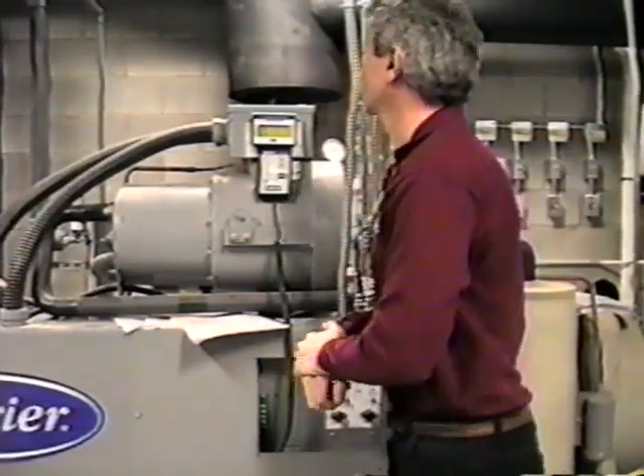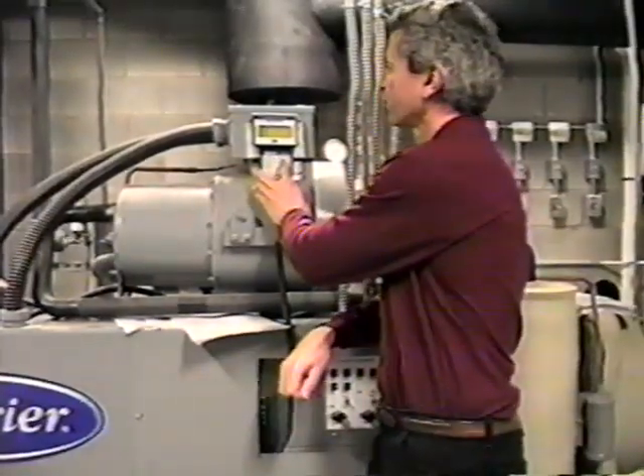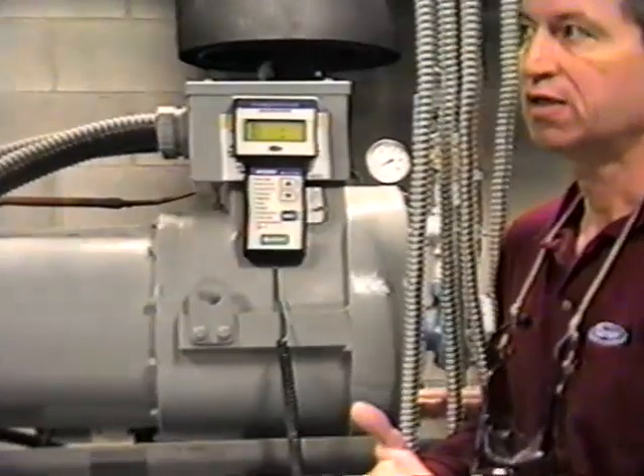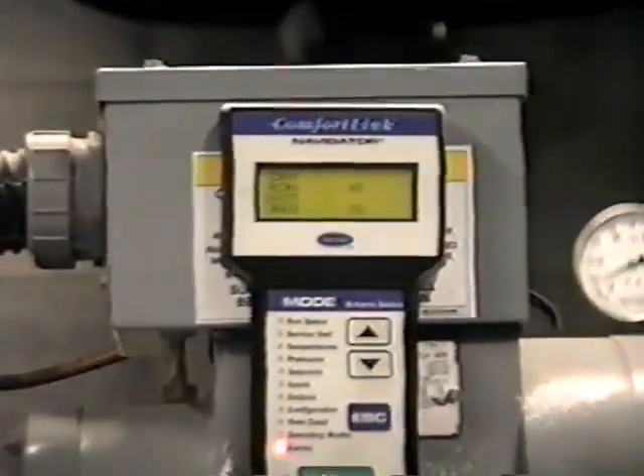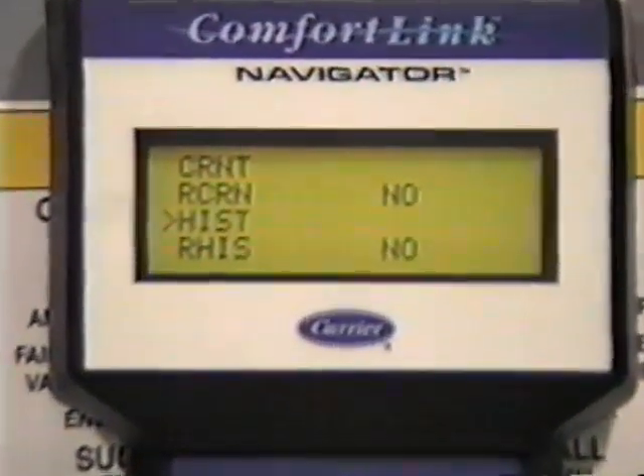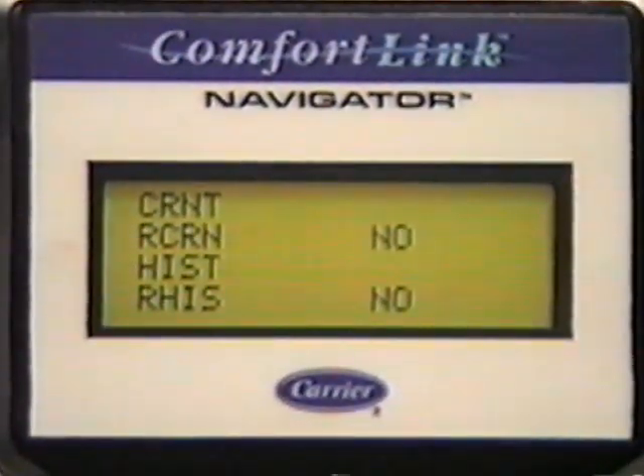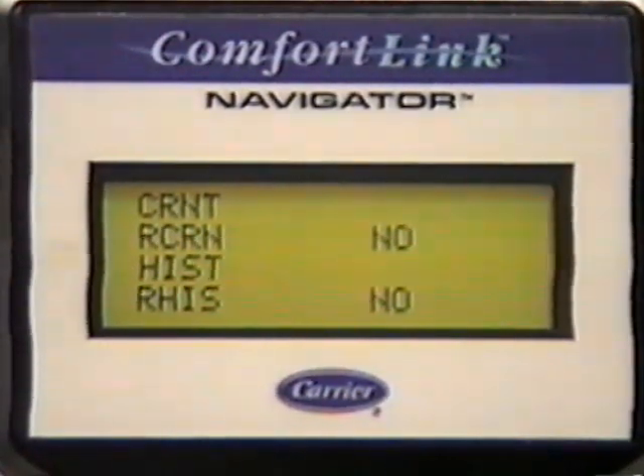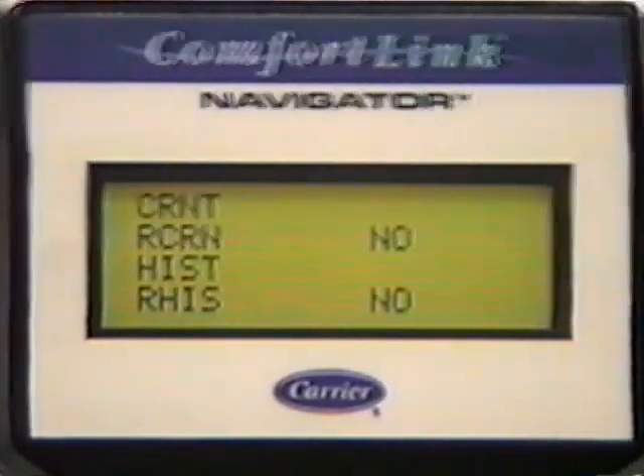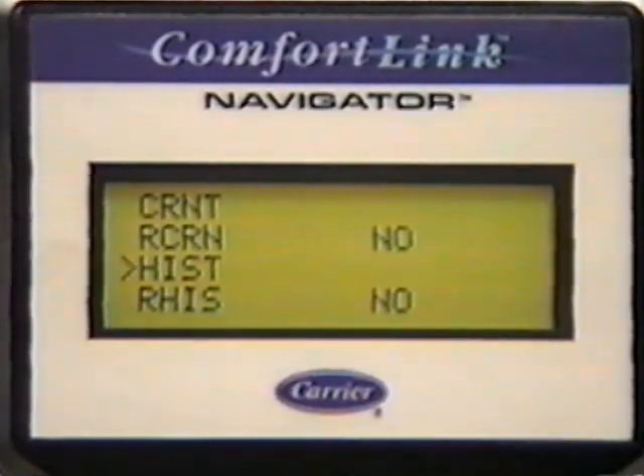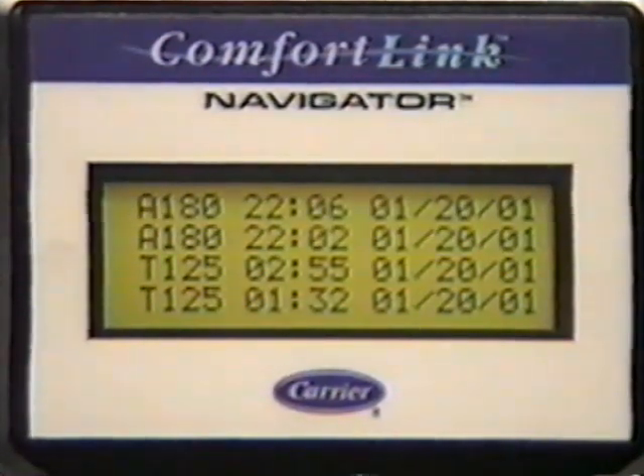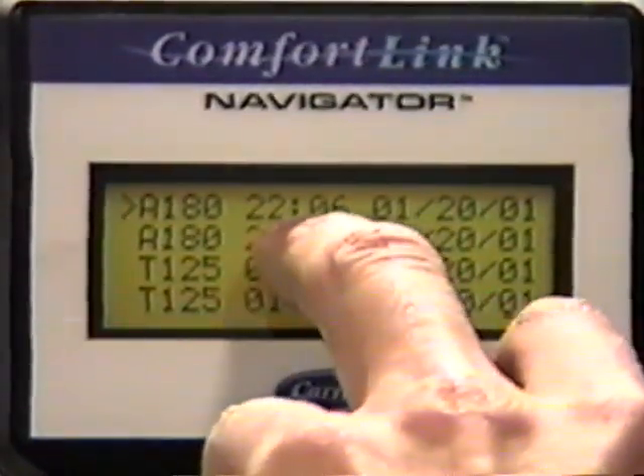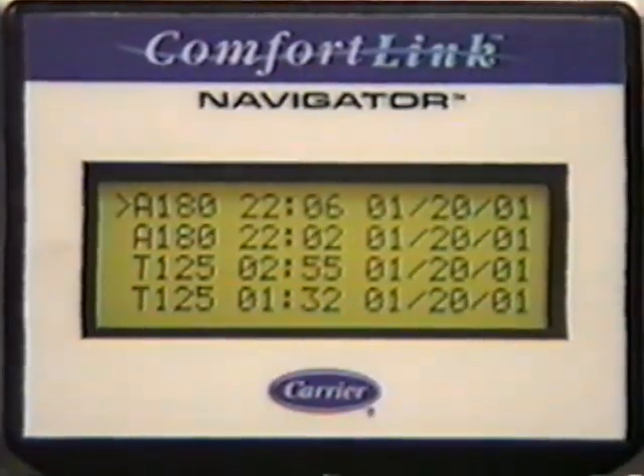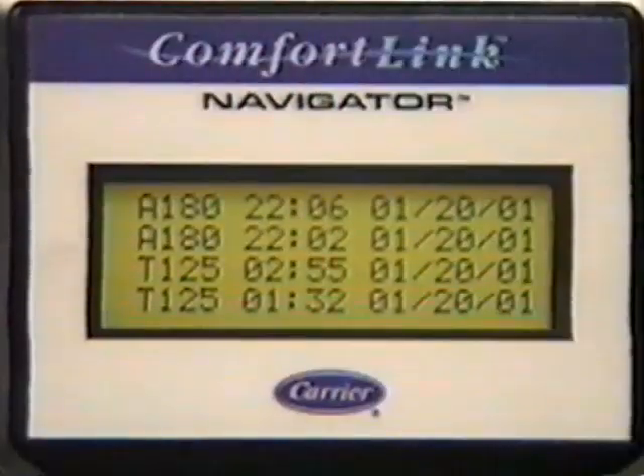Okay. Also on the alarm screen is a history. And that'll record, I believe, either 25 or 35 of the most recent alarms or alerts. Anything that causes the light to come on constantly or blink will be registered as an alarm or alert in the history. So to access that, you hit enter, and there you have a list. It stamps each one with a particular code, with the time and the date of that particular problem. And once it gets through the 35, it just overwrites the oldest one in there.